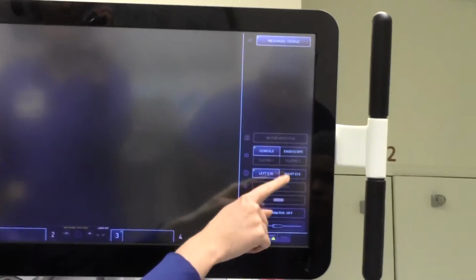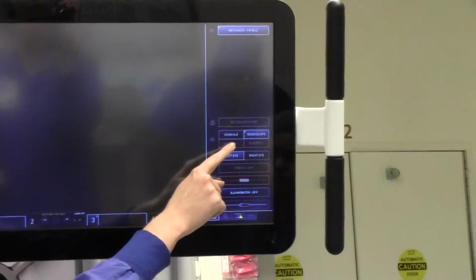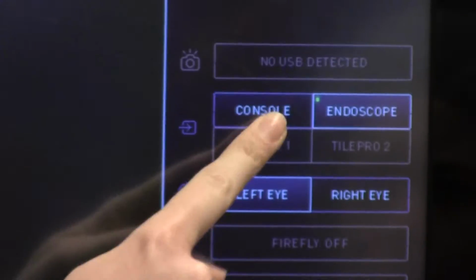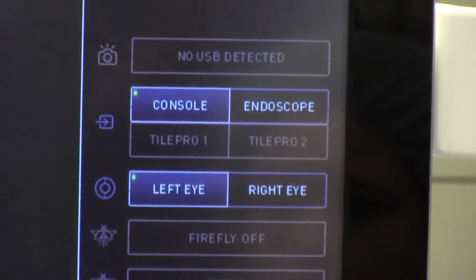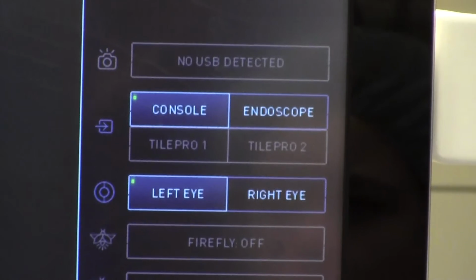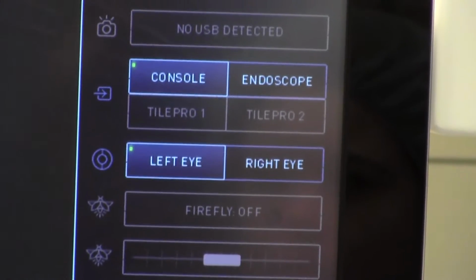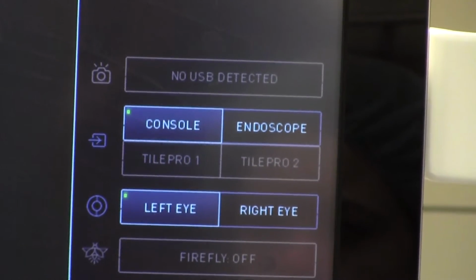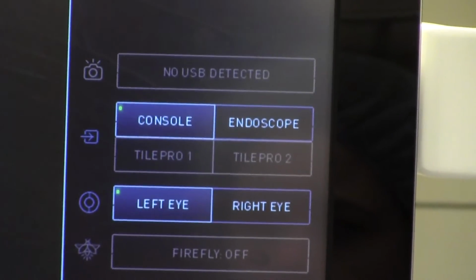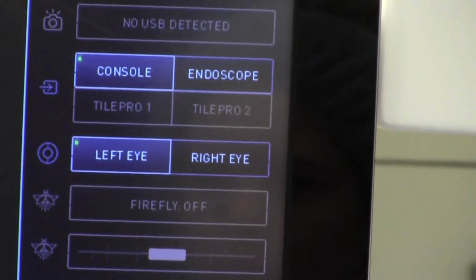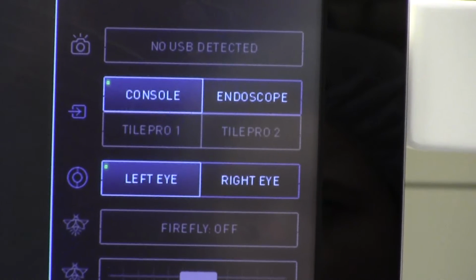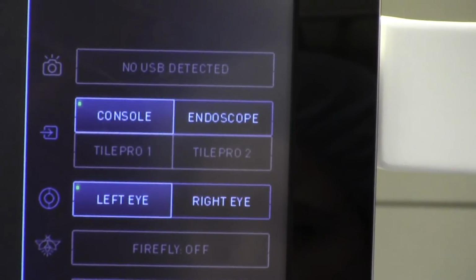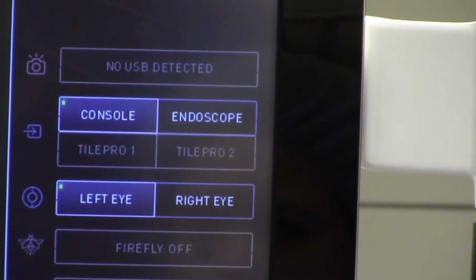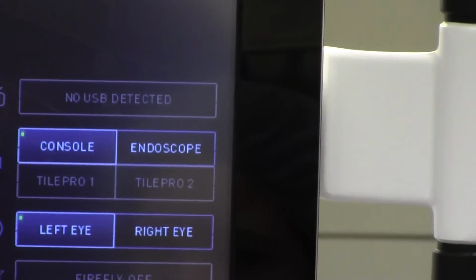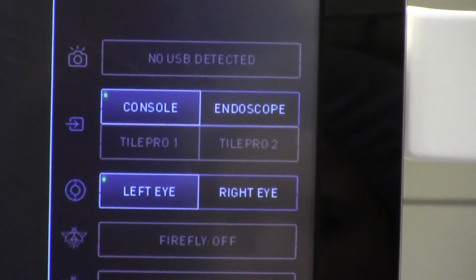Moving down, you have this little 4 square space here. It says console, endoscope, tile pro 1, and tile pro 2. It's always going to default to console view. That means you are seeing the exact same thing on this screen as the surgeon is seeing in the console, icons, messages, and all. I recommend just leaving it. Don't ever change that, because you get more information and you know what the surgeon's saying when you're looking at the same thing. Endoscope is going to take away most of the graphics, image, messages, things like that. They'll just go away. You'll just be seeing the view from the endoscope.